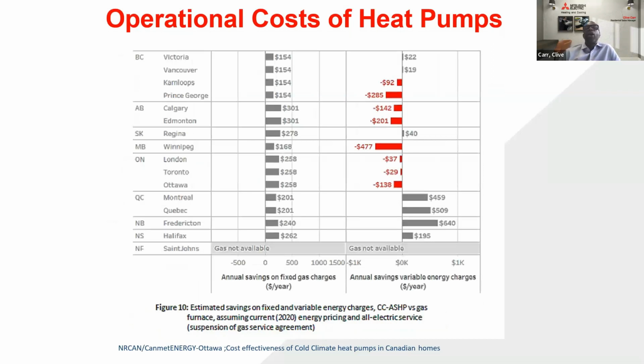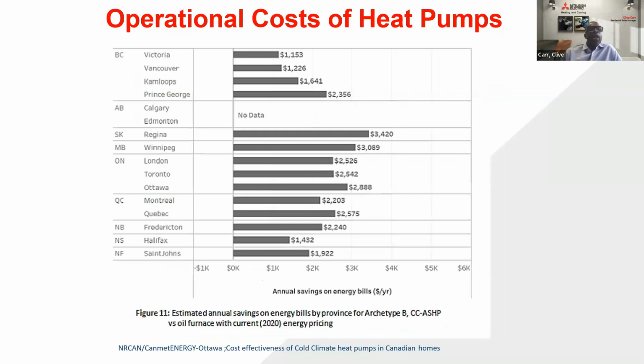So here we see another comparison of savings against natural gas based on the charges, right? Annual savings based on variable energy charges and annual savings based on fixed energy charges. So overall, in general, there isn't a major difference in the operating costs of using an air source heat pump versus using one of the cheapest forms of energy, which is natural gas.